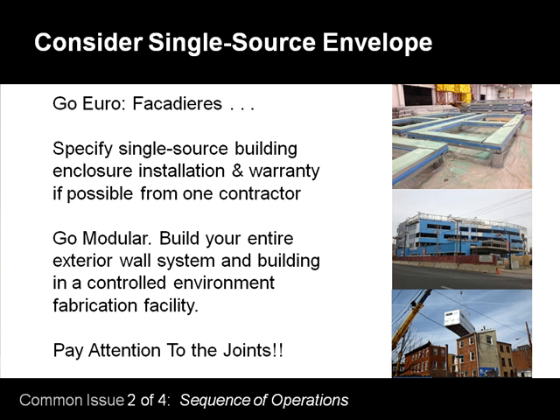So we're starting to see a lot more of that in particular markets in the United States, and certainly an interest in modularization of building enclosures, where the entire building enclosure is built off-site in a controlled factory and then delivered out to the field to be put together on-site. But really the moral of the story is continuity. We can't hammer that home enough. Continuity of trades is just as important as continuity of material. The more we can defragment all the people that are trying to put these together, the much more likely we are to have a complete air and vapor tight enclosure.